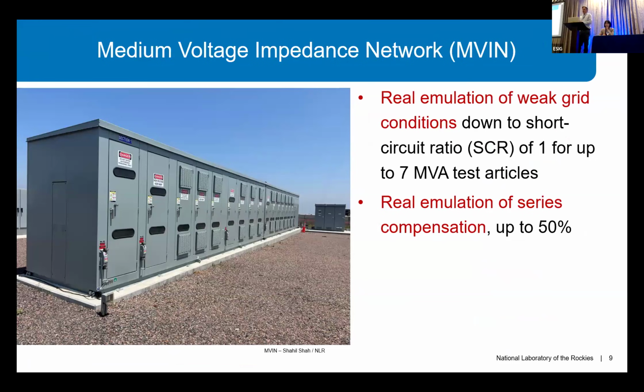Another unique piece of equipment we have is our medium voltage impedance network. So we can emulate impedance with the CGIs, but if we want real impedance or to validate our impedance emulation, we can insert this piece of equipment into the circuit, and it allows us to reproduce an SCR down to 1 for 7 MVA test articles. It also has series compensation capacitors built in, so we can do series compensation circuits as well.